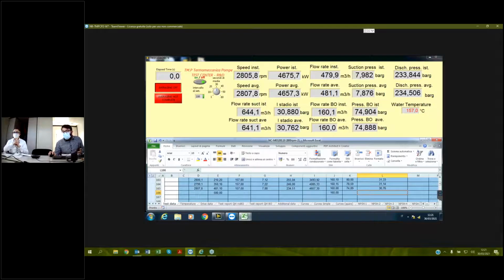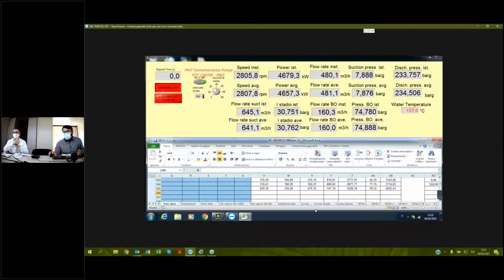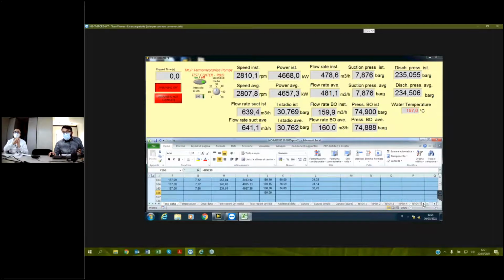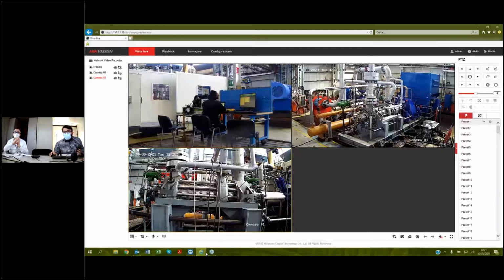Okay, immediately the calculation sheet gives us the results, the performance of the pump at the design condition. You know, total head, shaft power, efficiency, and others. Okay, now let's check together the vibration values and the noise with the help of my colleague directly on the pump.